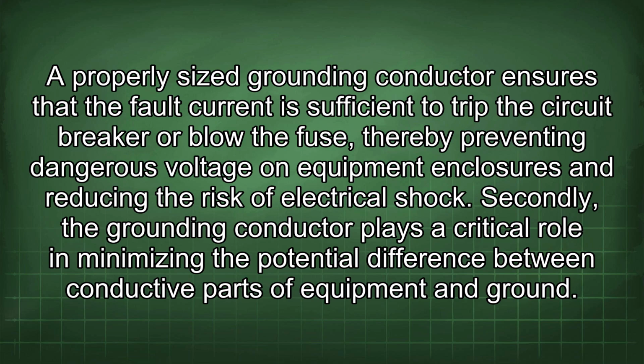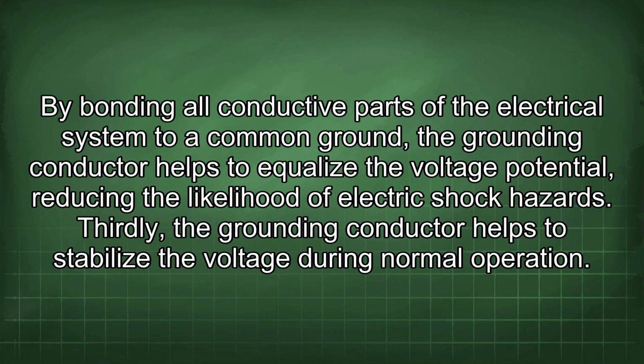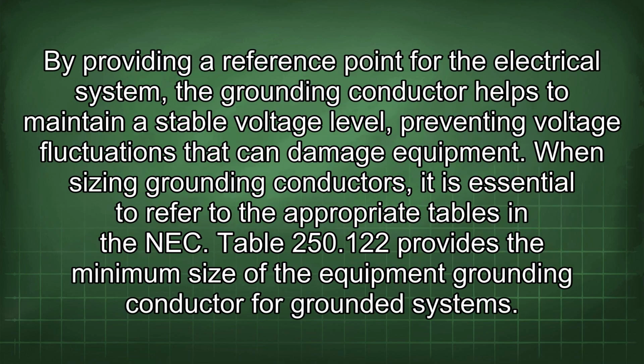Secondly, the grounding conductor plays a critical role in minimizing the potential difference between conductive parts of equipment and ground. By bonding all conductive parts of the electrical system to a common ground, the grounding conductor helps to equalize the voltage potential, reducing the likelihood of electric shock hazards. Thirdly, the grounding conductor helps to stabilize the voltage during normal operation. By providing a reference point for the electrical system, the grounding conductor helps to maintain a stable voltage level, preventing voltage fluctuations that can damage equipment.